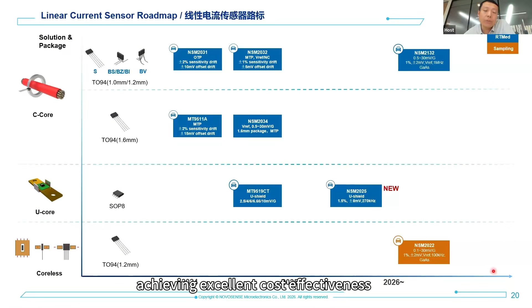This is one of the products that we are launching in the current sensing category. Traditional products designed for 1000 V systems may provide a creepage distance of about 8 millimeters. The key advantage of this product is that it extends the creepage and insulation distance from 8 millimeters to 15 millimeters, with a basic insulation working voltage of 2,800 volts.